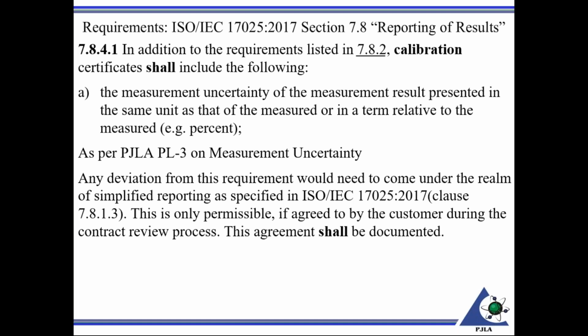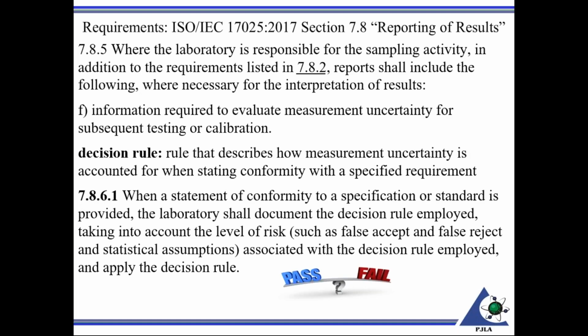However, if need be, you would still need to be able to go back and duplicate, save enough data, where need be, to go back and ascertain what the measurement uncertainty would be. And we're going to talk about the decision rule there. If the customer does not require measurement uncertainty, that does not alleviate the lab's responsibility for the decision rule as well. We're going to get to that here real shortly.